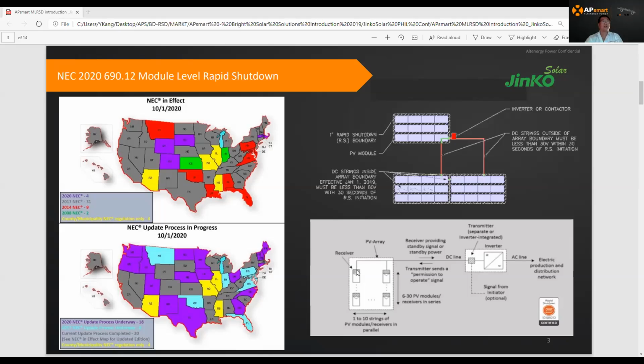When the receiver receives the signal, it turns on the PV module power output. When rapid shutdown is initiated, the transmitter stops outputting power and stops sending the signal. If there is no heartbeat signal, the receiver shuts down the module right away. So that's the whole process.